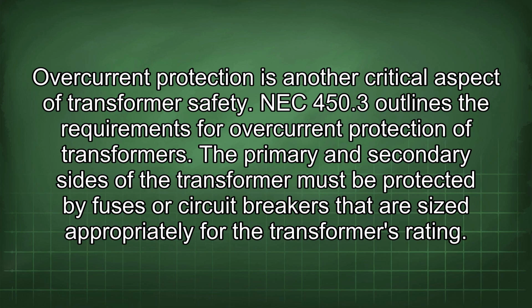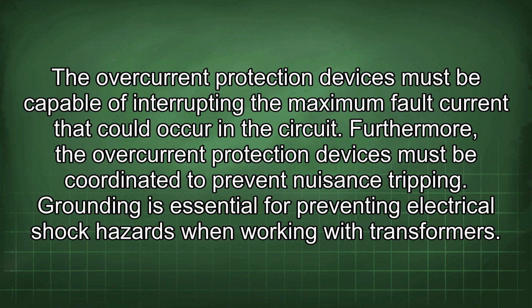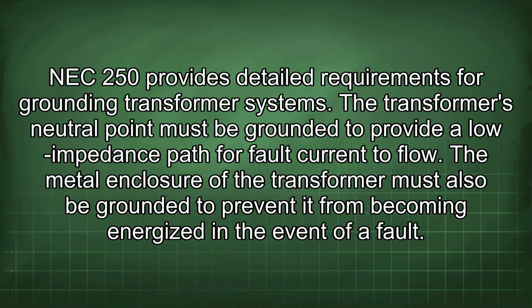The primary and secondary sides of the transformer must be protected by fuses or circuit breakers that are sized appropriately for the transformer's rating. The overcurrent protection devices must be capable of interrupting the maximum fault current that could occur in the circuit. Furthermore, the overcurrent protection devices must be coordinated to prevent nuisance tripping. Grounding is essential for preventing electrical shock hazards when working with transformers. NEC 250 provides detailed requirements for grounding transformer systems.